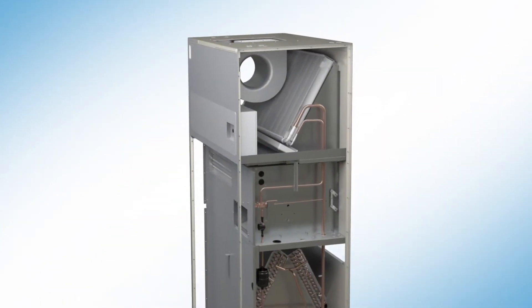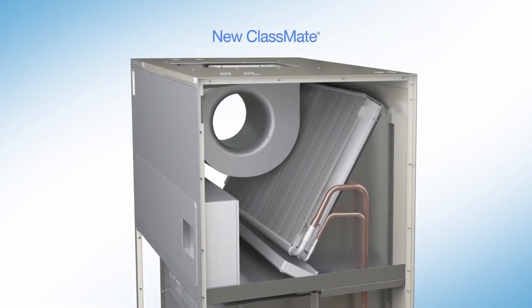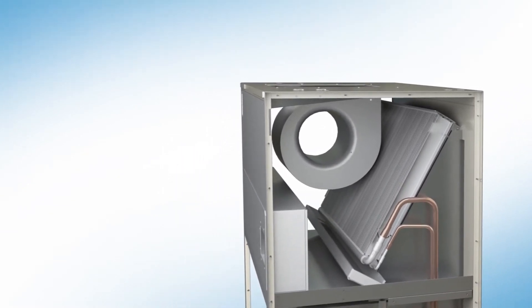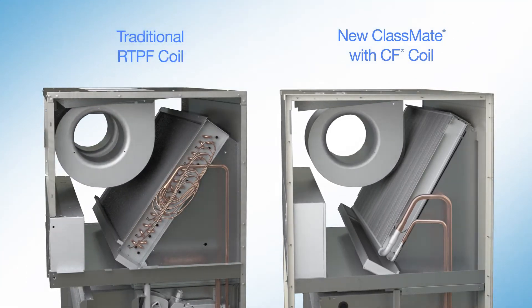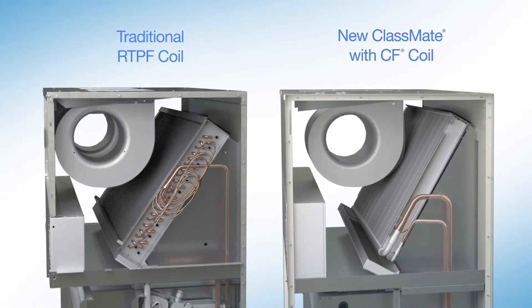Its dual-purpose condenser evaporator offers indoor cooling and heating capabilities for a 20-30% COP improvement and a reduced airside pressure drop for less fan power consumption. The CF coil is more compact than round tube plate fin coils for a smaller footprint that allows outdoor air heat recovery with a 100% economizer in the same compact cabinet, as well as multiple heat exchanges for cooling, heating, and reheat.